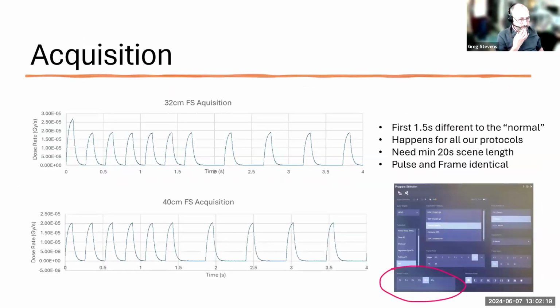For acquisition, you might notice that the initial run runs at a faster rate than the actual reported run, and you will need to increase the scene length, which I've circled at the bottom. Otherwise, you're not going to get the correct dose values, and obviously you've got to stop measuring that fast pulse rate. So here, it's about 2 seconds. This is for our neuro protocol.